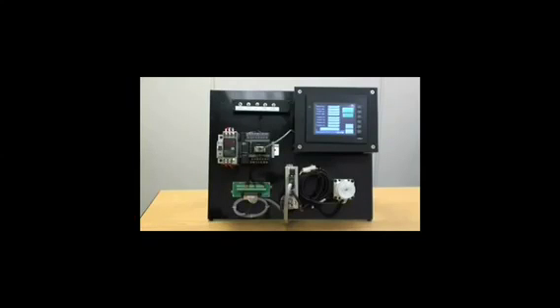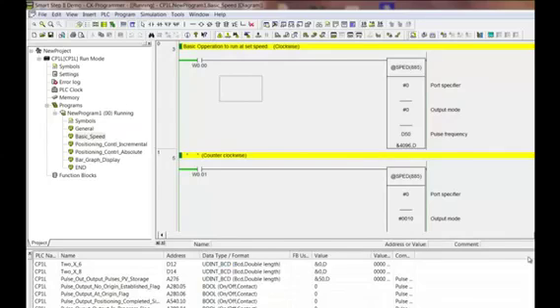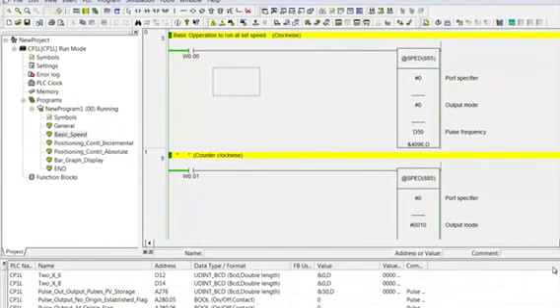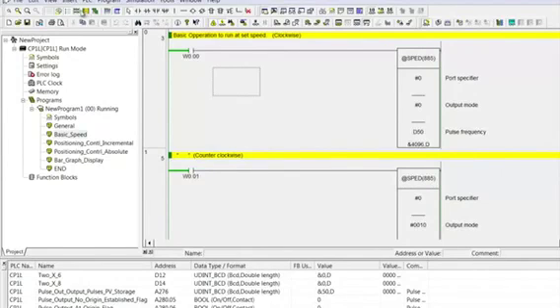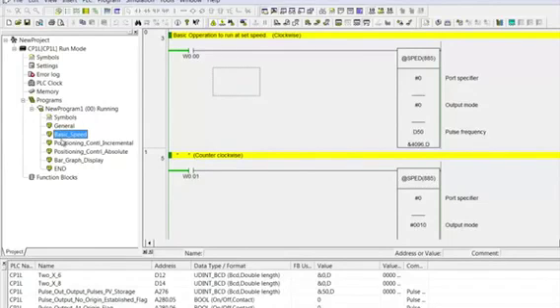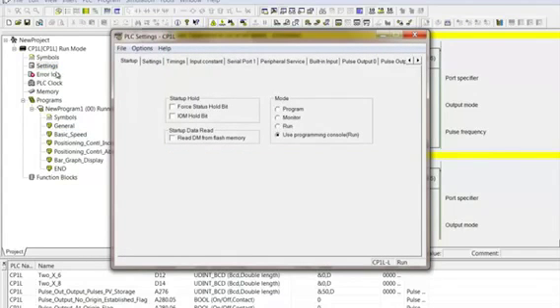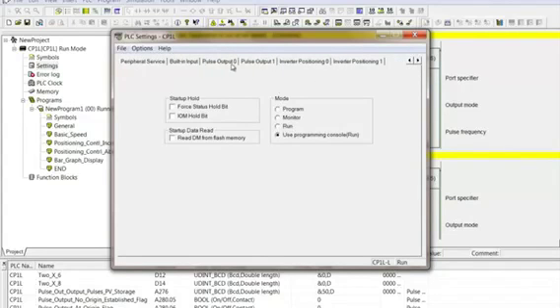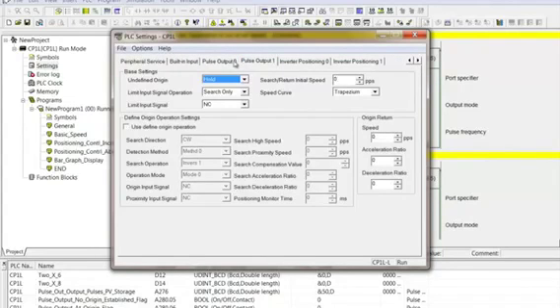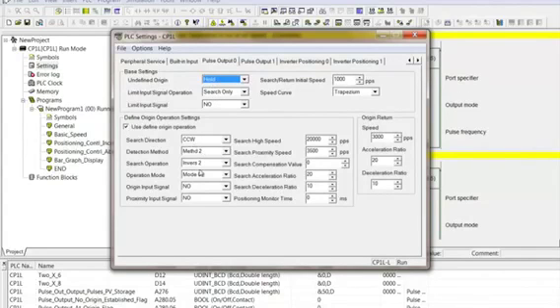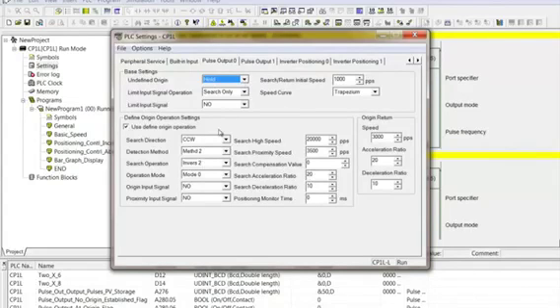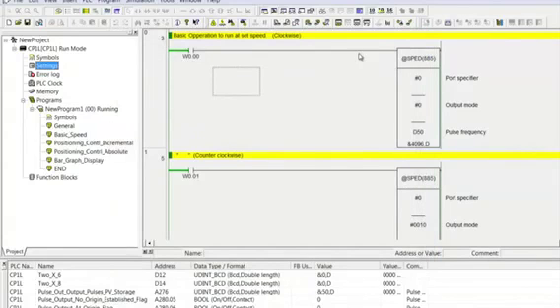And in the final section here, I will go in and show you a little bit about the ladder code in the programming environment and that will conclude our session. In this last section, we'll do a very brief review of some of the instructions that were used. We're looking at CX programmer here. The project tree consists of many of the typical things you would see in a PLC program and my code sections are in through here. I'd like to go back just for a second though and talk about that subject of homing that's set up back here under the PLC settings. And that can be found under the pulse output control. And here you see the various options that you have for setting the homing routine. This correlates back to the time chart patterns that we reviewed earlier on. So this is set up here and then it's really just fired from an origin instruction, which I'll show you in a minute.